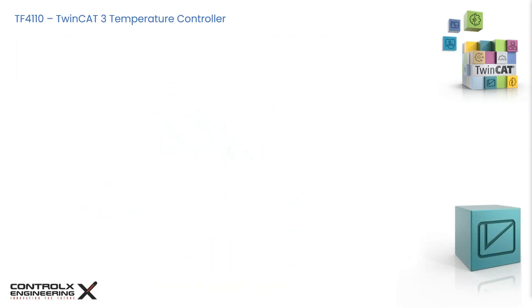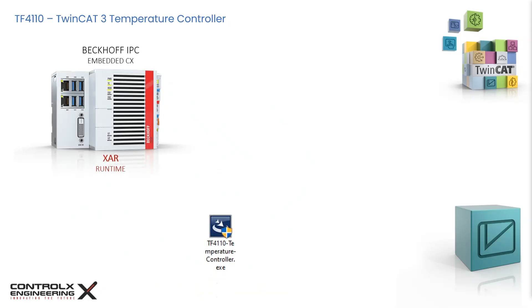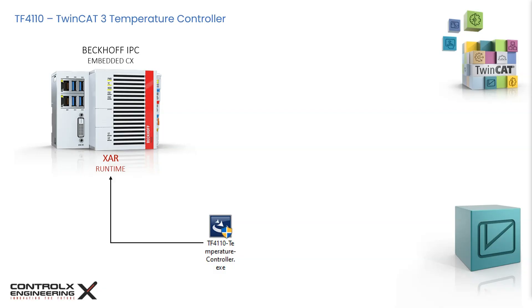In order to use the TF4110 temperature controller function, the executable that we just downloaded must be installed on the TwinCAT XAR Runtime IPC. This is where the PLC logic is executed. In addition, the appropriate license for using this function must be purchased from Beckhoff. But for testing and development purposes, we will make use of the 7-day trial license, which grants us full access to the temperature controller for a period of 7 days.